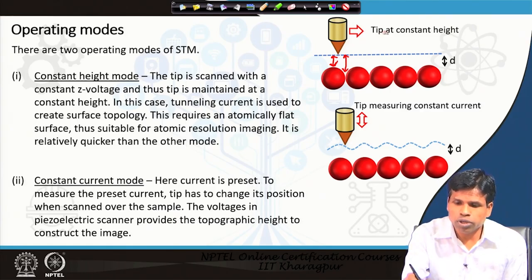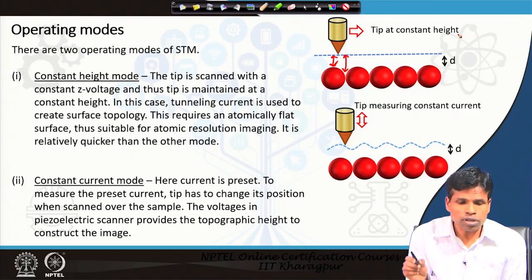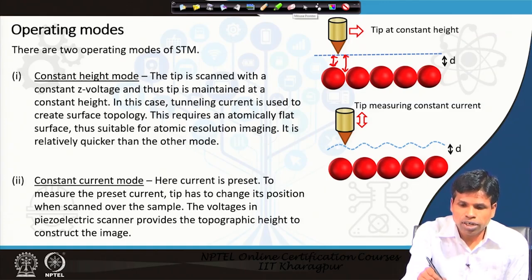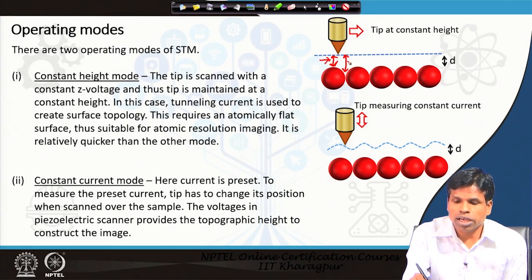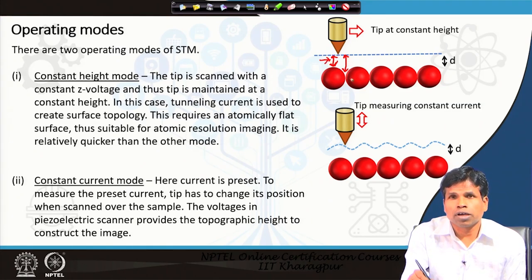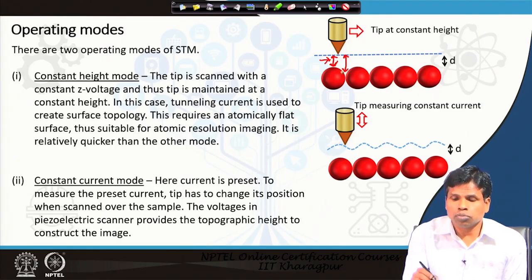In constant height mode, the tip is at constant height and scanned above the sample. We get different tunneling currents — high tunneling current where the distance between tip and sample is small, and low tunneling current where the distance is larger. This tunneling current is used for imaging purposes. So we get the surface topology from the tunneling current data in this case.